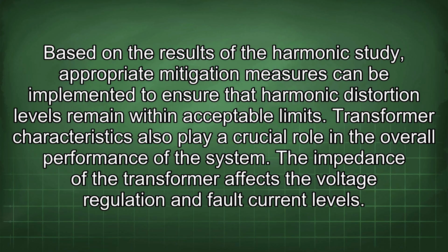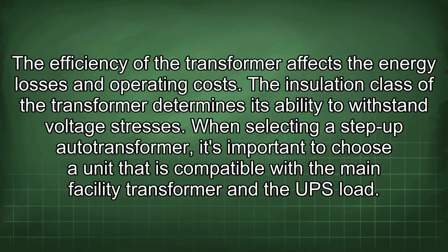Transformer characteristics also play a crucial role in the overall performance of the system. The impedance of the transformer affects the voltage regulation and fault current levels. The efficiency of the transformer affects the energy losses and operating costs. The insulation class of the transformer determines its ability to withstand voltage stresses.